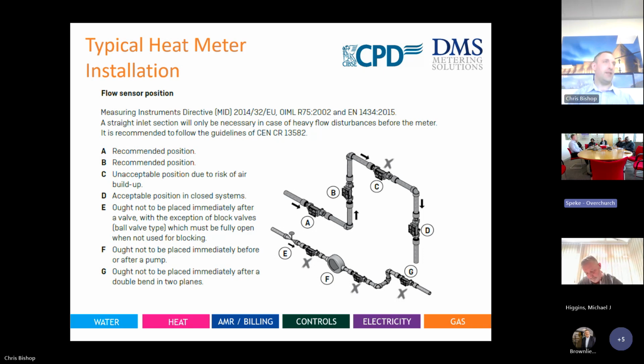But like I say, recommended positions here. We have to think about high point, and the purpose of high point is that air, oxygen, finds its way to the highest point of the system. That could be the roof space, or within a plant room, it could double bend up and go to the ceiling itself. If there are no air vents on that part of the section, it's going to find a chamber to sit in, and that's generally going to be a heat meter body, a mechanical body, anything like that.